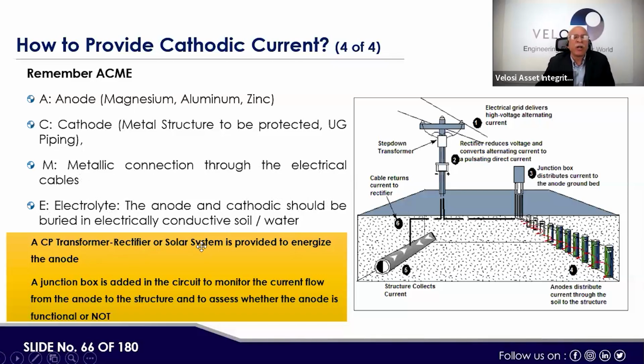A CP transformer rectifier or solar system is provided to energize the anode. A junction box is added in the circuit to monitor the current flow from the anode to the structure and assess whether the anode is functional or not.